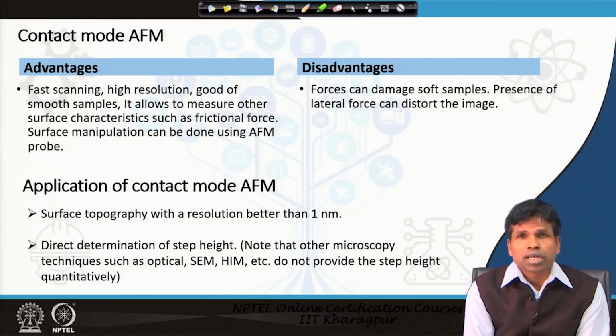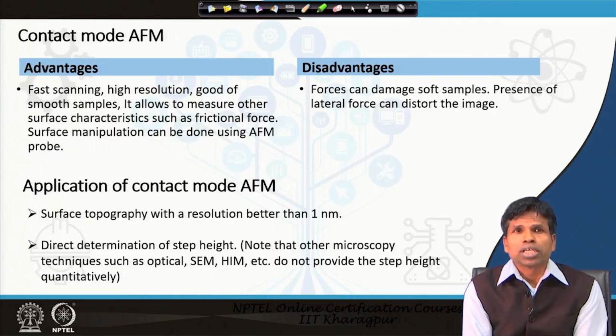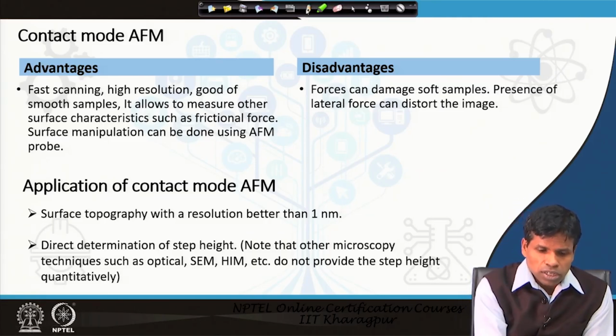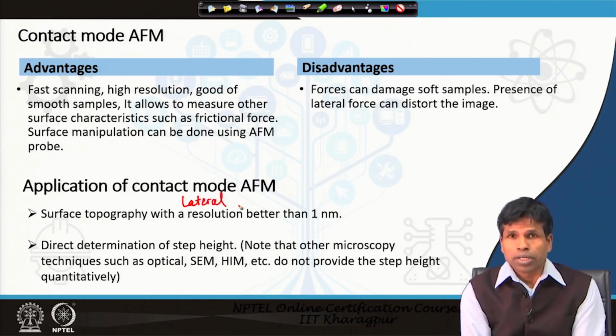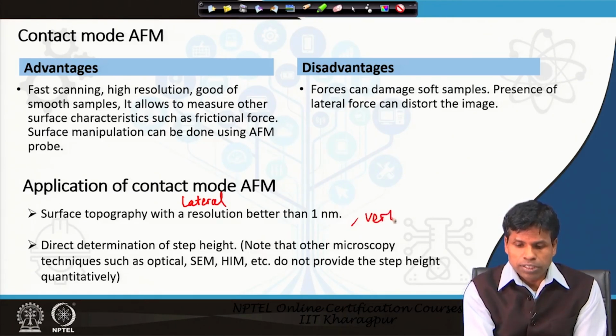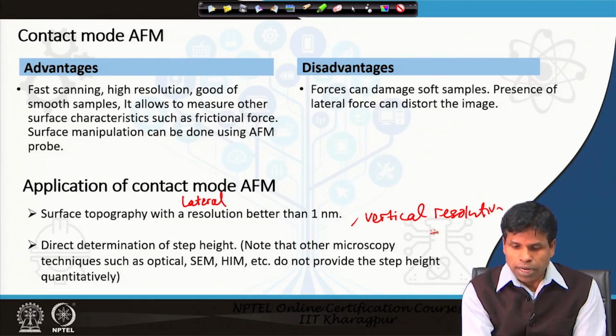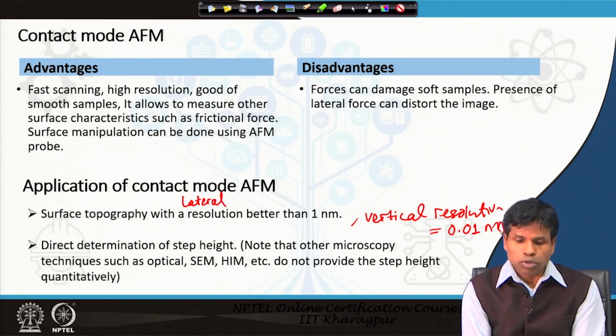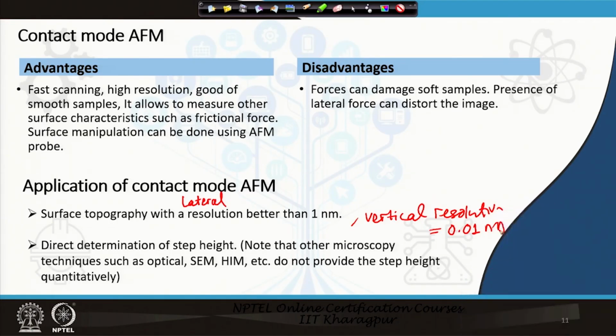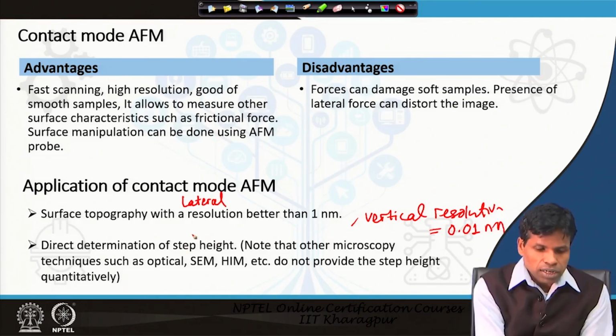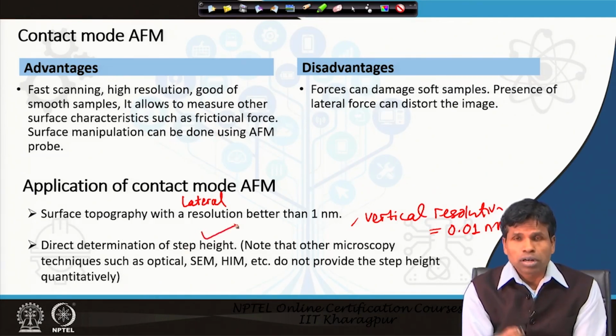As far as the application of the contact mode of AFM is concerned, certainly we can get surface topography with lateral resolution better than 1 nanometer, and vertical resolution around 0.01 nanometer. Vertical resolution is always higher in atomic force microscopy, and here we can directly determine the step height or thickness of the monolayer if it is a 2D material.